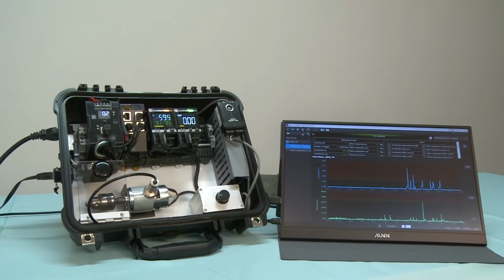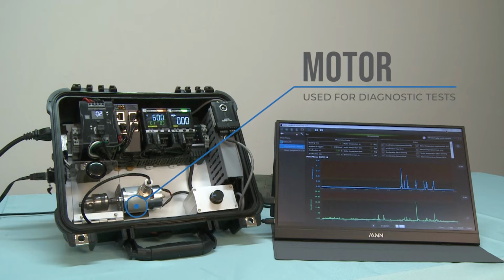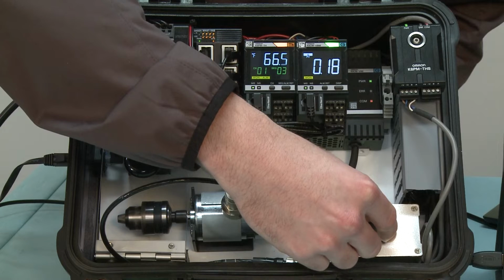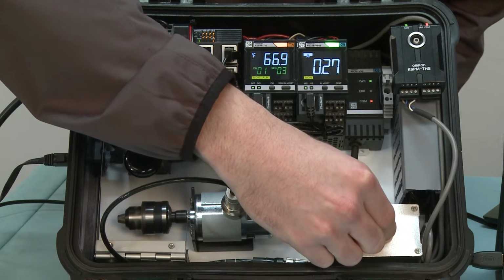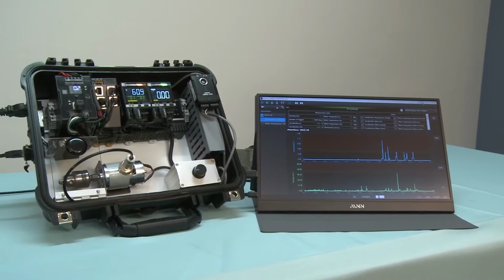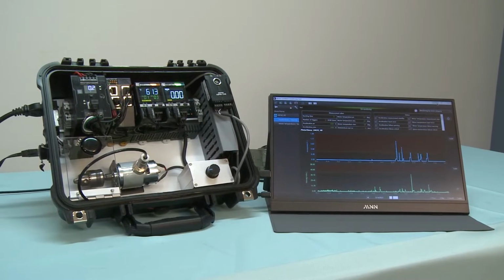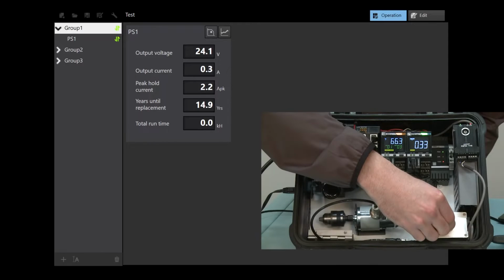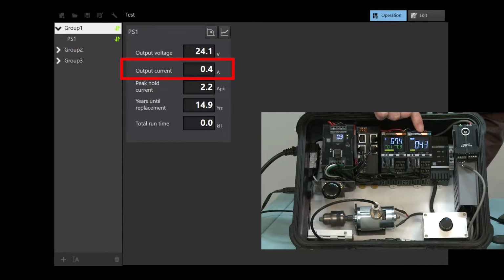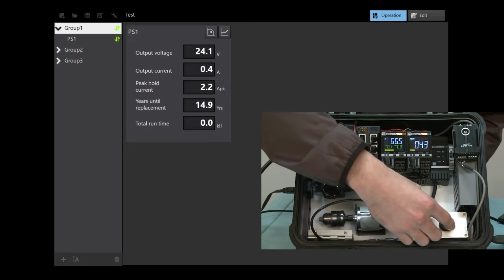Let's take a look at my system. I have a motor that's powered by my S8VK-X. Let's say I need this motor spinning at exactly this speed. Now check out the real-time data on the software. My output current amps are around 0.3. With that number in mind, I'm going to set my output current to 0.4, so that's the threshold, the highest threshold.